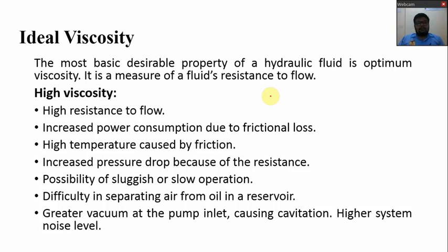Increased pressure drop because of the resistance to the fluid. Possibility of sluggish or slow operation, because the fluid will move slowly. Difficulty in separating air from oil in a reservoir, because the viscosity of the oil is very high, so if any air bubbles or particles are present in the oil, they are very difficult to remove.